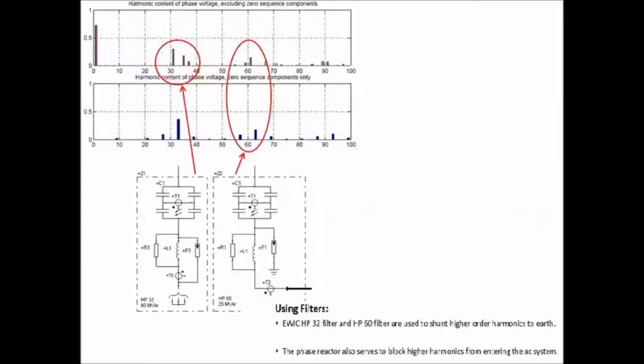Then we've also got side filters, the 32nd and the 60th, which I'd already talked about. These are to shunt the higher order harmonics down to earth. And we also have the transformer delta windings, which are able to take care of those triplen harmonics, so it substantially absorbs them as well. And obviously there's the 5.8 on the Irish side and the 23rd on the UK side.